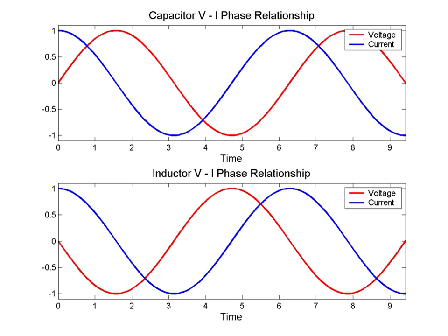Impedance measurement in power electronic devices may require simultaneous measurement and provision of power to the operating device. The impedance of a device can be calculated by complex division of the voltage and current. The impedance of the device can be calculated by applying a sinusoidal voltage to the device in series with a resistor, and measuring the voltage across the resistor and across the device. Performing this measurement by sweeping the frequencies of the applied signal provides the impedance phase and magnitude.